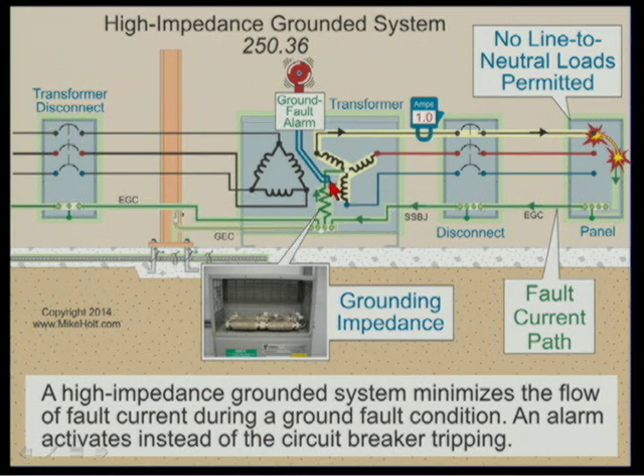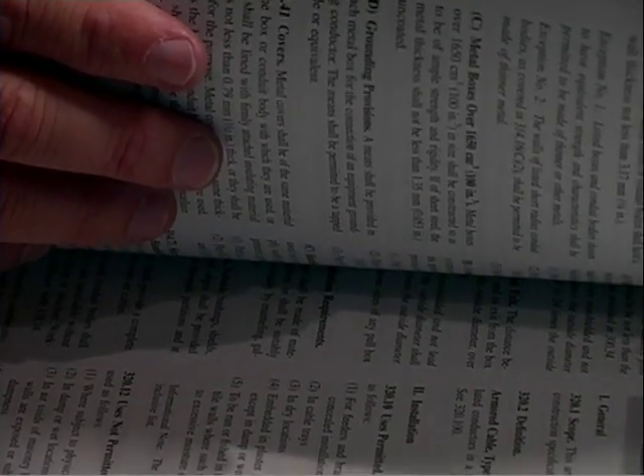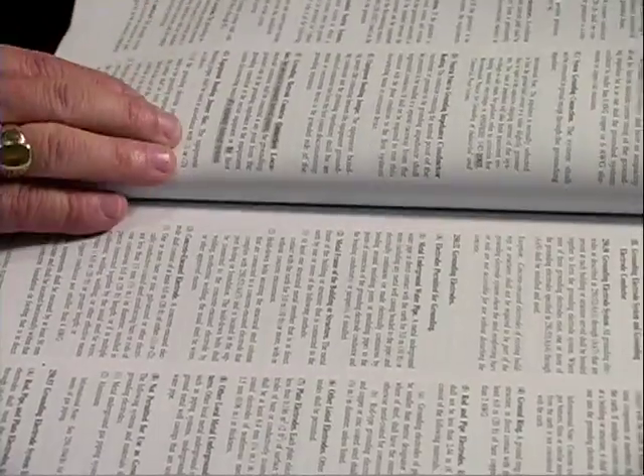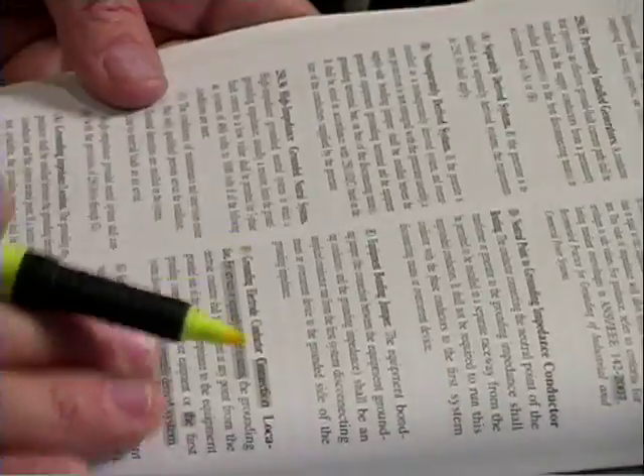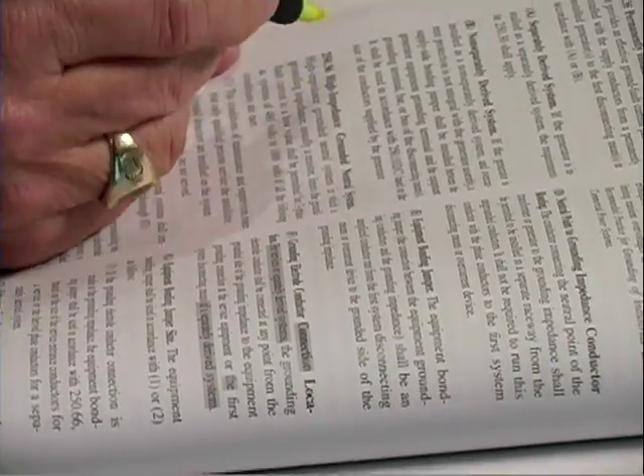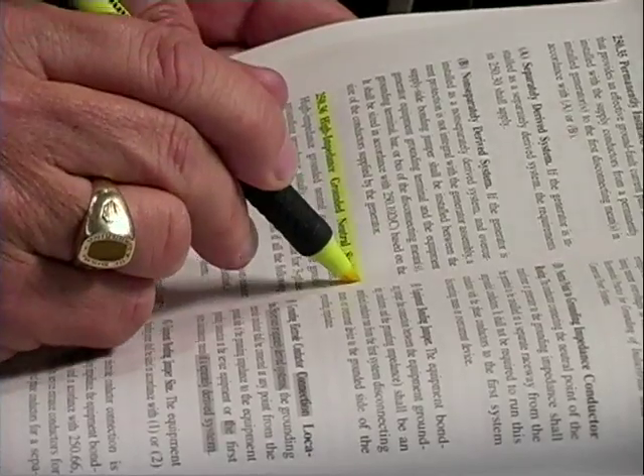Even though they talk about this being a high resistive grounded system, in fact, what does the code call this? 250.36. Does it call it a high resistive neutral system? Didn't you say impedance grounded? Just resistance grounded. Let's see. I thought they called it somewhere a neutral grounded system. A high impedance neutral, 250.36, yeah, page 116. High impedance, right, grounded neutral system. Well, that's what I thought.